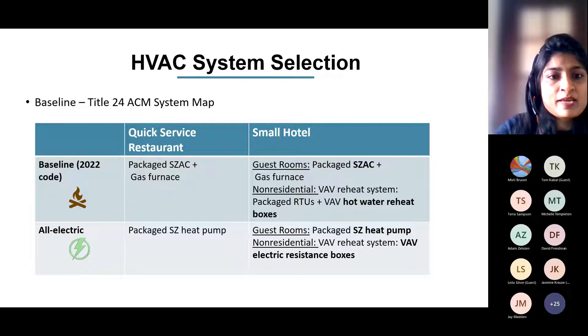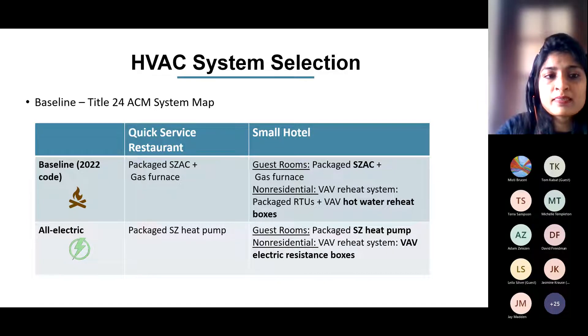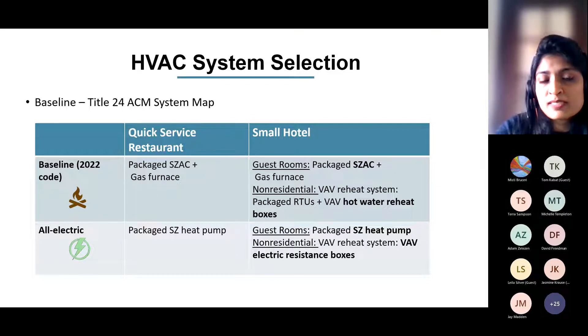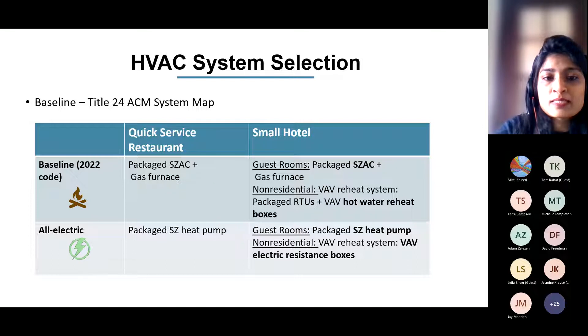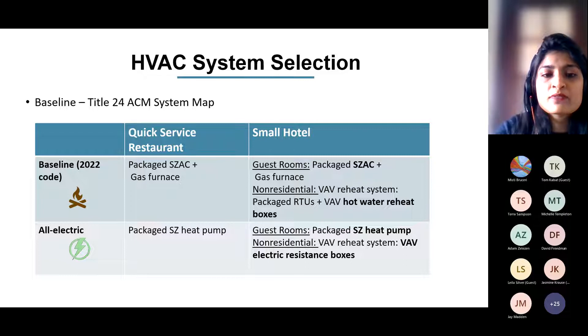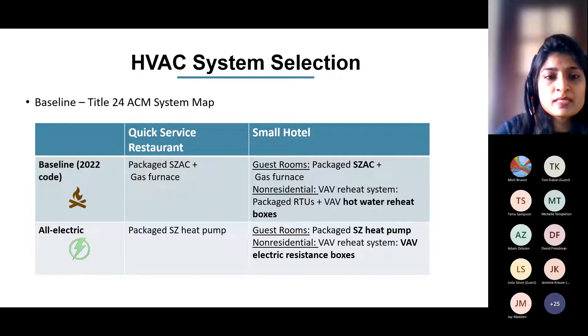For restaurant, the baseline is a packaged single-zone system with AC and furnace, and the proposed is a packaged single-zone heat pump for both dining and kitchen. For small hotel, guest rooms are served by packaged single-zone units and non-residential areas use a variable air volume hot water reheat system. The all-electric scenario uses single-zone heat pump for all guest rooms and VAV electric resistance boxes for non-residential areas. Here, electric resistance boxes are more practical since there are very few non-residential areas served by VAV boxes.